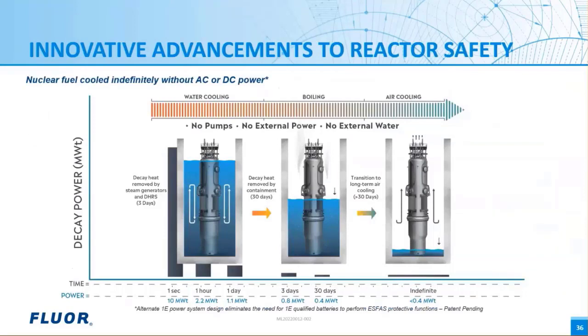This next slide emphasizes the triple crown of safety achieved by NuScale. What is the triple crown? It means that to safely shut down and cool the NuScale reactor, you need 1, no operator or computer action, 2, no AC or DC power, so no pumps, batteries, or backup emergency generators, and 3, you need no additional water. The water in the reactor pool is sufficient for the cool down into perpetuity. So the reactor is known as what's called walkaway safe. And this is a first for the commercial nuclear power industry.